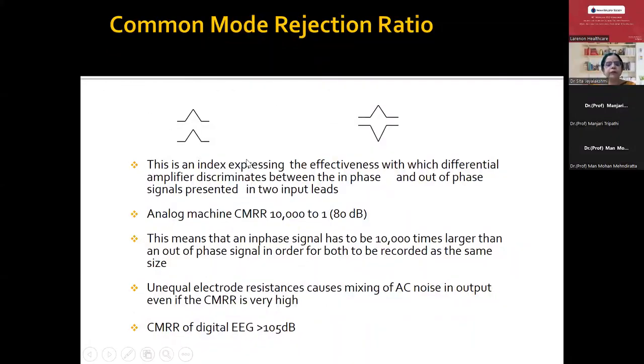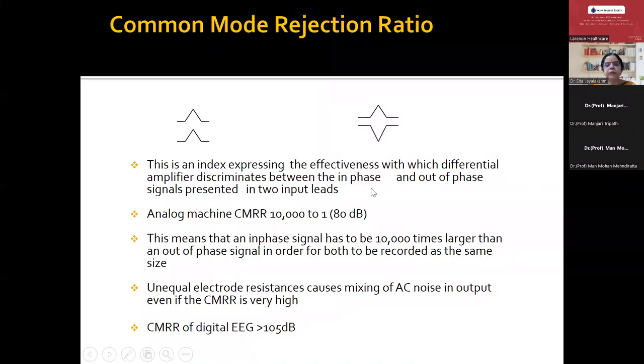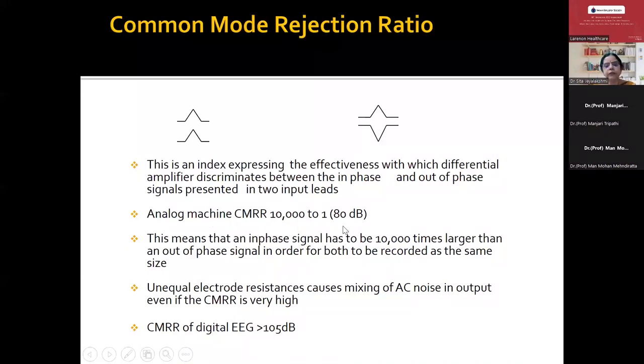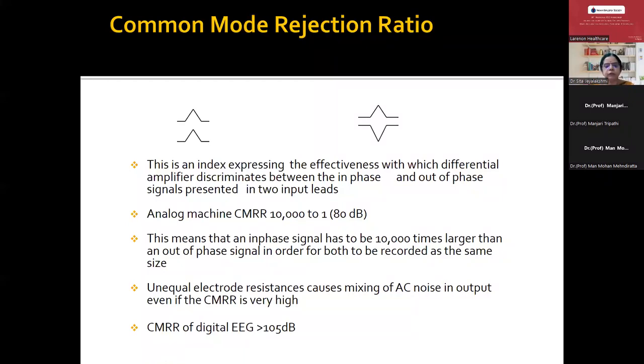Coming to the common mode rejection ratio — CMRR. It is the effectiveness with which differential amplification occurs and how the amplifier discriminates between the in-phase and out-of-phase signals presented in two input leads. This is very important when selecting an EEG machine. CMRR should be at least 80 decibels — nowadays we get machines with more than 100 decibels. The CMRR of a digital EEG is usually more than 105 decibels.